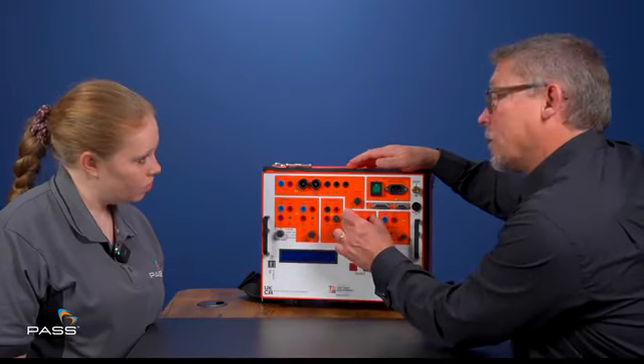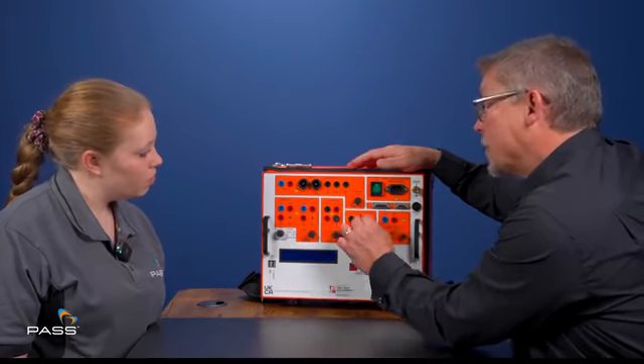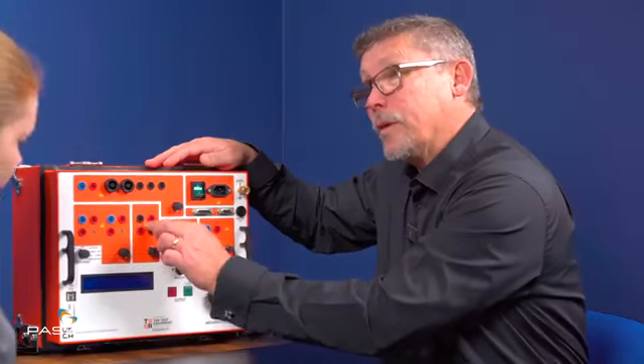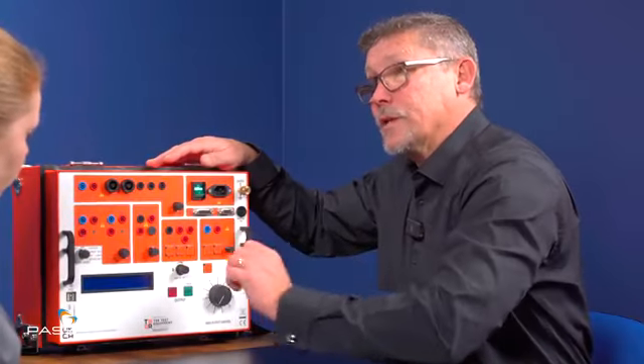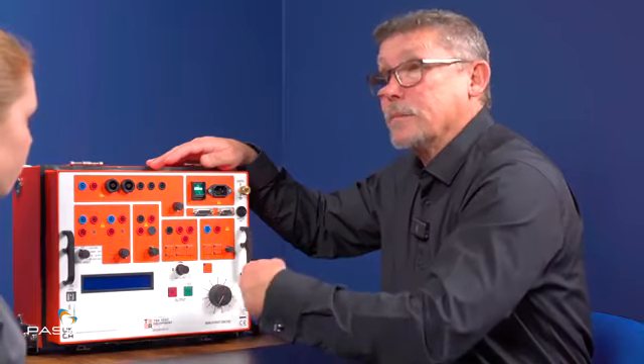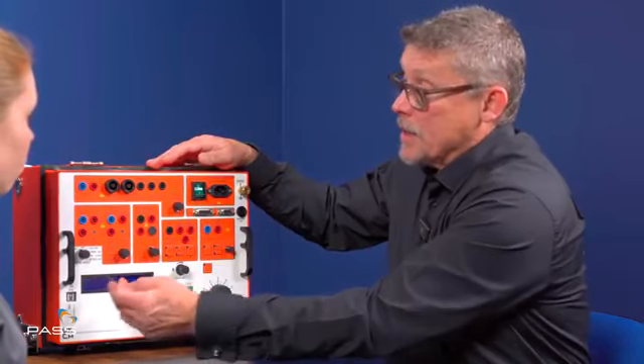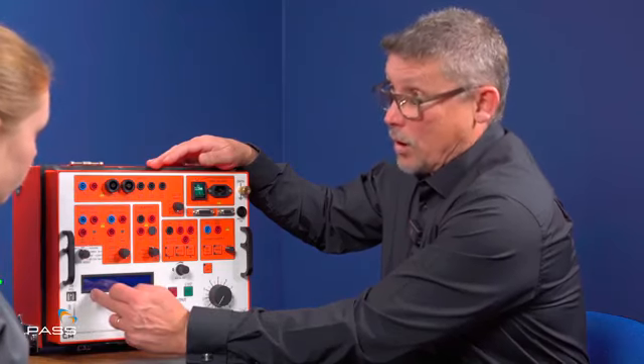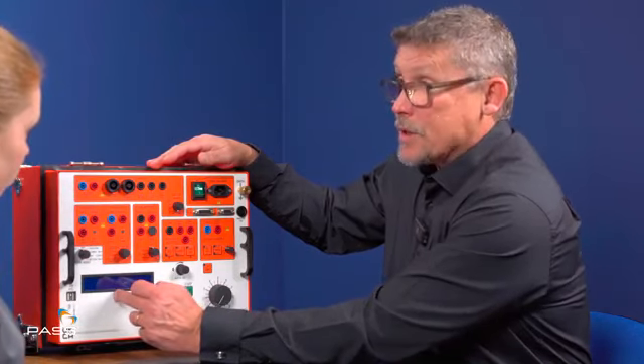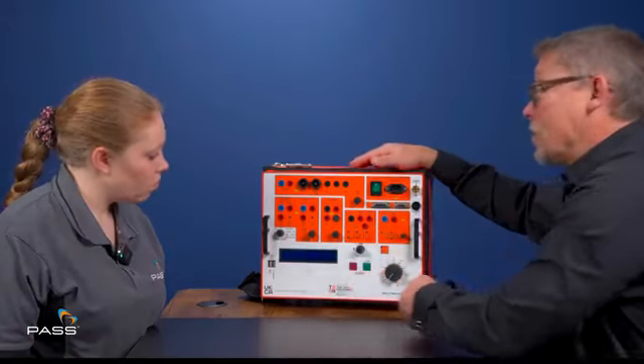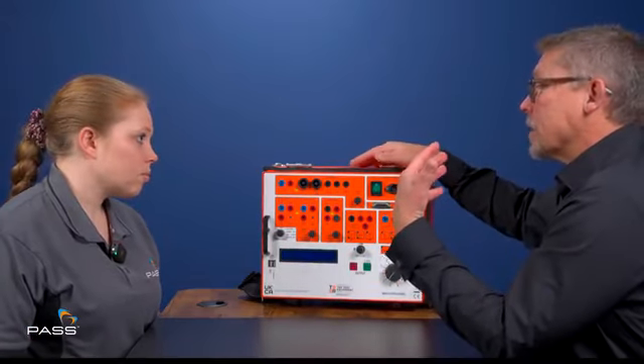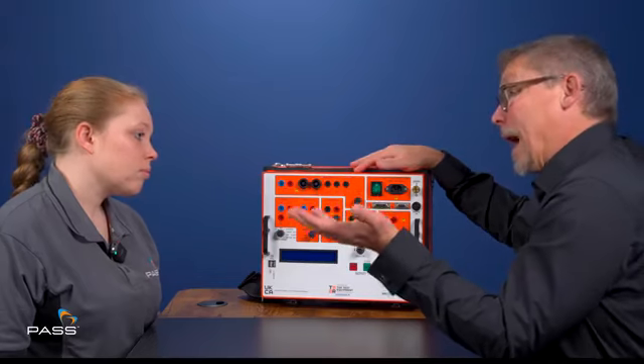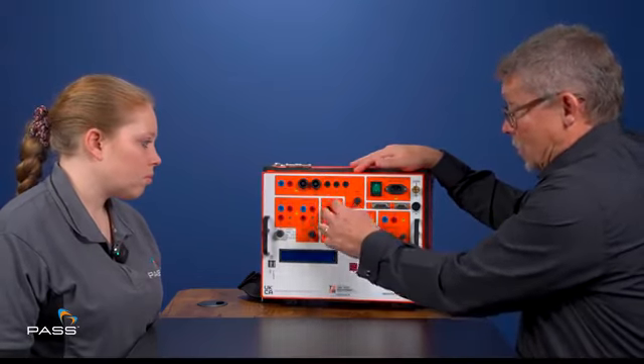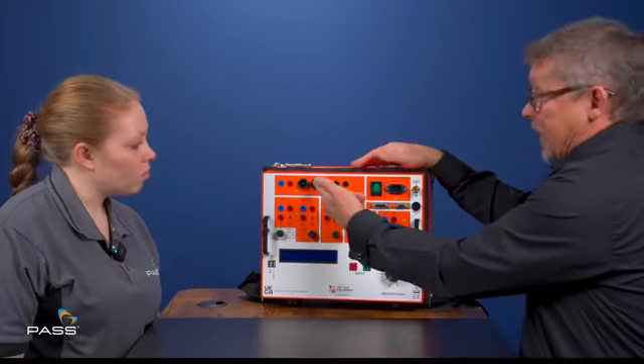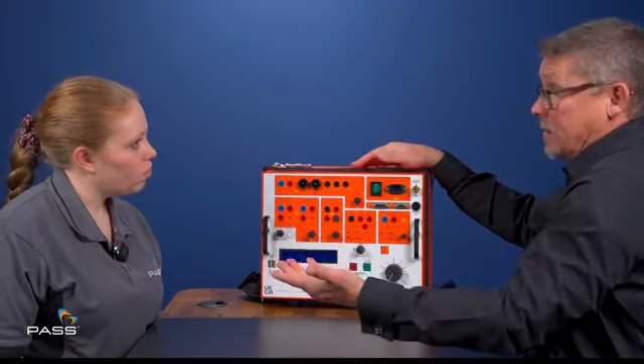If I'm using this aux channel, the auxiliary channel is blind. So we're using that to meter this. So we put it through the multimeter here and we reference it to this, and we can then use that to measure AC parameters. It'll be either volts or current in this. It'll be frequency and phase angle. We can also use it to measure power. Now, there's a relay called an impedance relay or power relay. So we can use that to look at this, look at that, and therefore that's our current, that's our voltage, for example. Ohm's law, we can then use it to measure power.